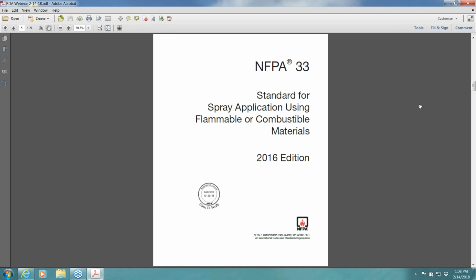After that, it's going to be your local building code. They're all going to reference the international building code for the most part, but then, say, North Carolina has a building code that they put above the international building code. So you have to navigate through some of those questions to make sure the product not only meets all the listings and requirements for its construction, the booth itself, but also that where it is installed meets all the proper building codes—especially something called egress, which is NFPA 101 life safety, meaning you've got to have a way to get out of the booth and a way to get out of the building. You can't block the exit of the building, those types of things.